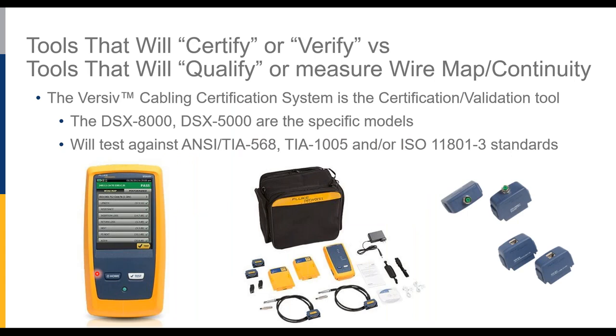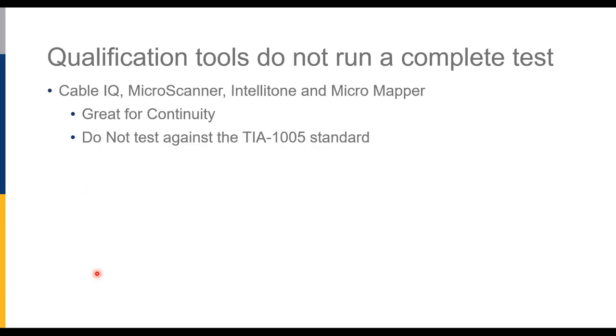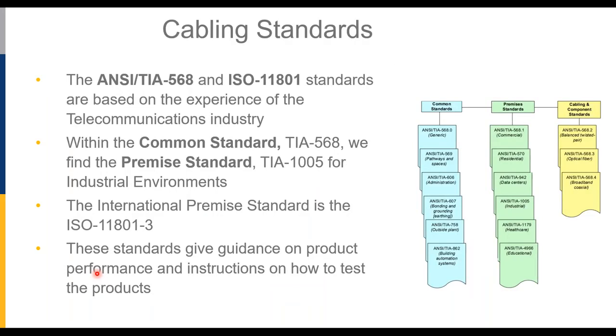An important distinction: in the telecommunications world we talk about certifying cabling, while in industrial environments people often talk about verifying cabling. A DSX-8000 or DSX-5000 can measure against the standards that an Ethernet application requires — not just checking continuity, but also noise on the cable. Simpler qualification tools can tell you if the cable goes from point A to point B, but may not tell you the distance to where a cable is open. These tools are helpful for day-to-day management: is there a switch on the far end? What's the distance to where the cable is open?